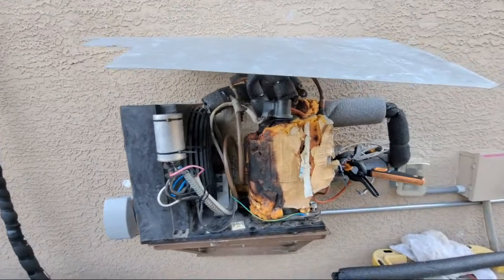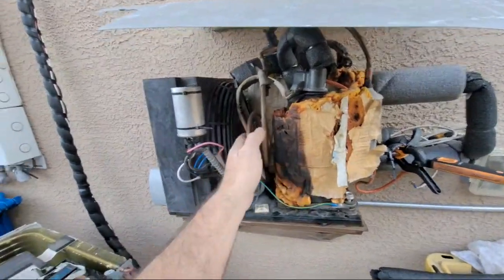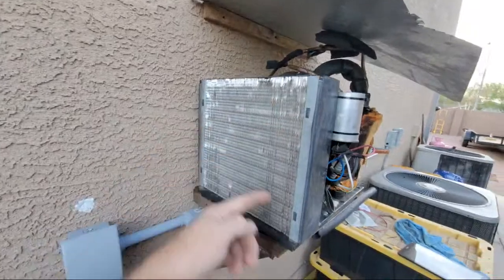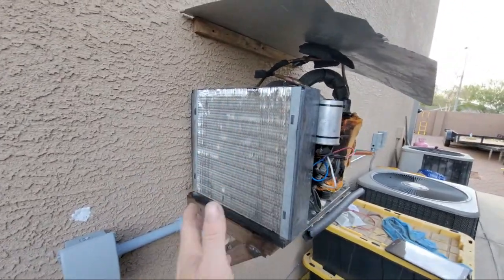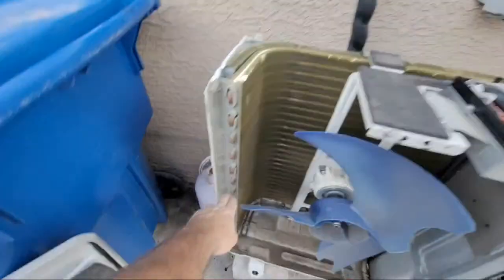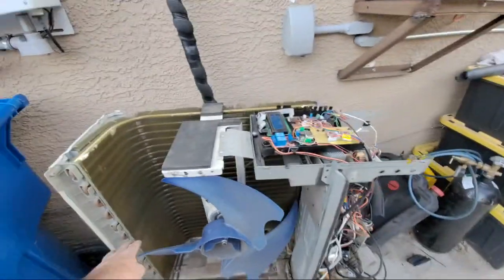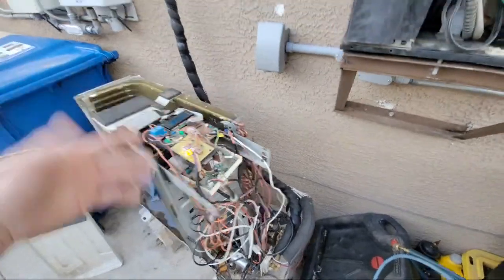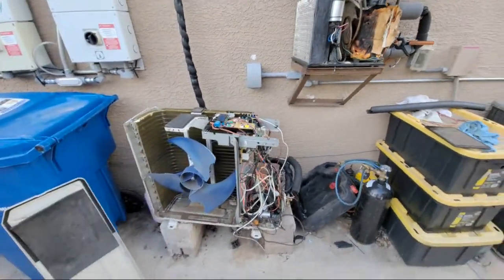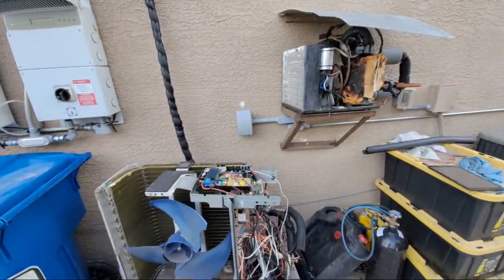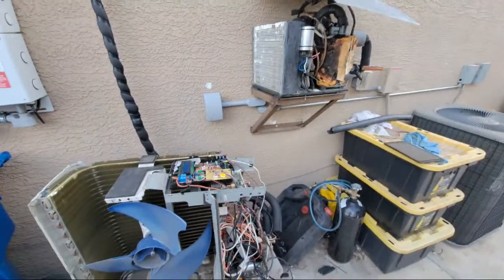And this thing kicks ass for heating the water. It's weird because look at the surface area. It's 2 rows. This was a condenser coil, turned into an evaporator coil. And then I have the top 2 circuits, 2 more rows of it, thinking that it should be great, a little more surface area. It won't run as cold, but what happened was it wound up running way longer.